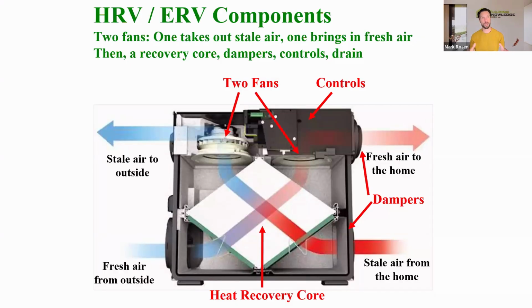We need to help people understand these boxes are the lungs of the home. Their role is to extract stale air from the house and replace it with fresh air in a balanced way, meaning exhaust air out equals air in, so no pressure is generated on either side. They add the extra benefit of heat recovery, or in an ERV's case, heat and moisture recovery, to save energy. We're spending energy to have fresh air, but we want to save as much as possible by stealing back heat from the exhausted air and transferring it to the incoming fresh air, reducing the burden on heating systems.